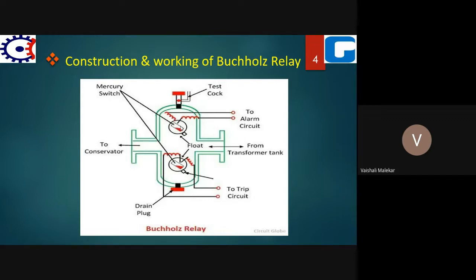But if a severe fault is there, like a phase to earth fault, or faults in the tap changing gear, then the volume of gas will be large. If a major fault is there, the production of gases will be more, and due to that the float at the bottom of the chamber gets tilted and the trip circuit gets closed. Now the trip circuit will operate the circuit breaker, and as the circuit breaker operates, it will isolate the transformer from the supply. So this is the working of the Buchholz relay.